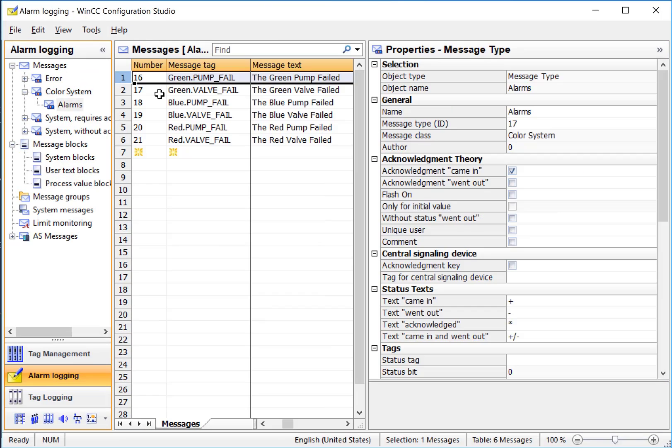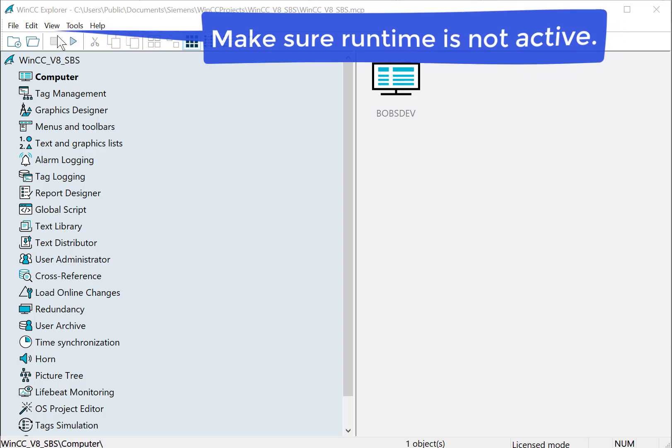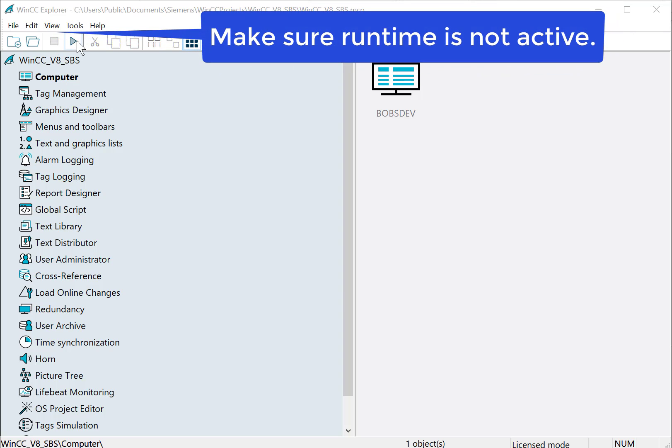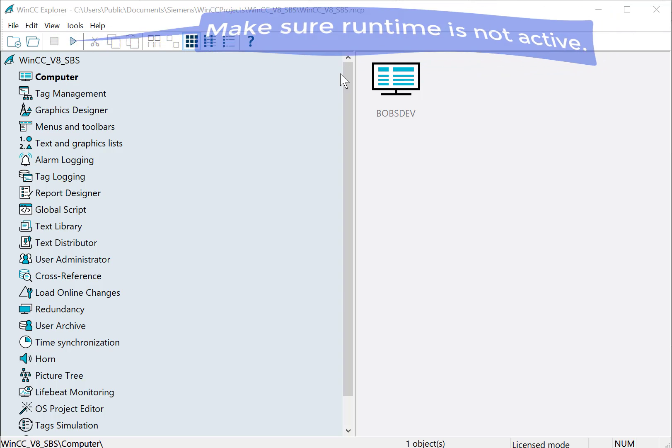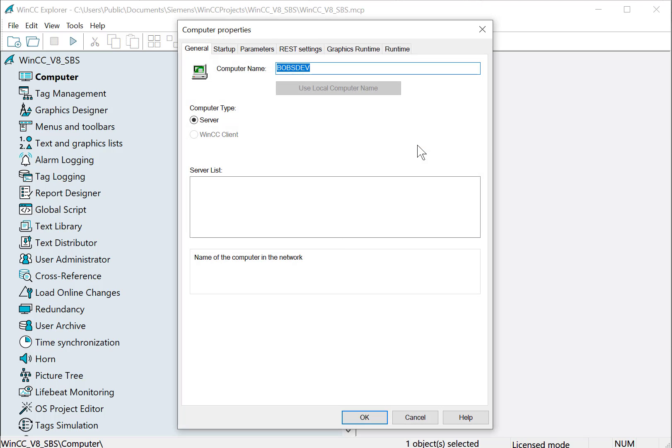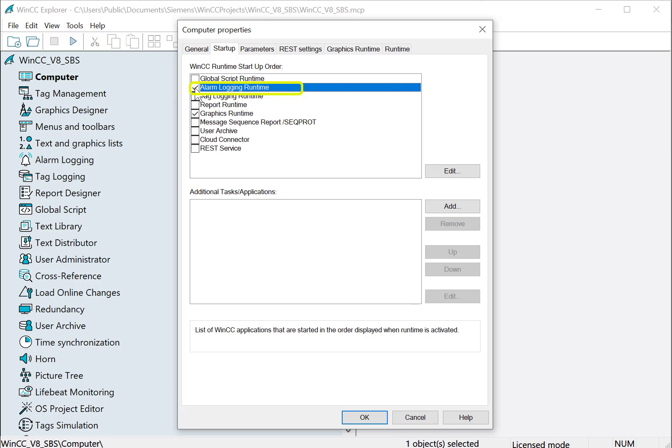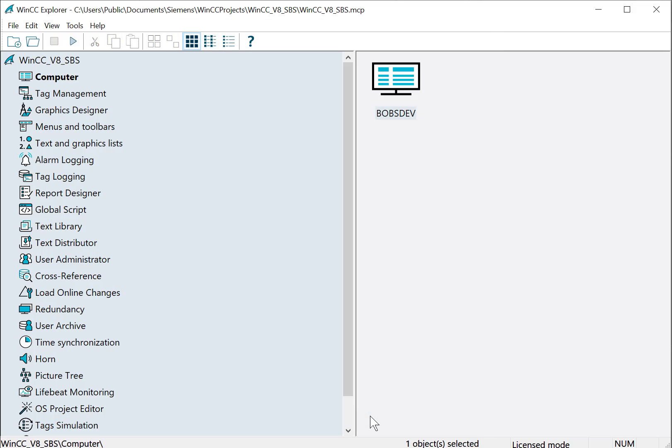So that's it for now in Alarm Logging Editor. The next step is to go back to WinCC Explorer. Make sure you are not in runtime. Go to Computer and your Project Server, and then we'll go to the Startup tab. Here is where we turn on the alarm system, so we just check it and click OK. If you do this during runtime, you'll have to stop runtime and restart it for it to take effect.